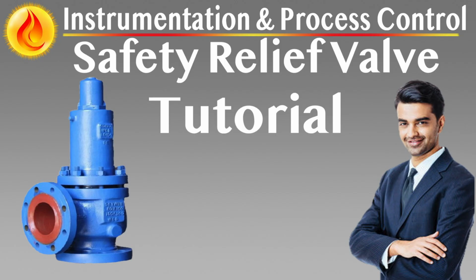Regulatory and code compliance. Air-assisted relief valves are not defined in most pressure vessel codes, e.g. ASME Section 8. Their use may require approval from local authorities or independent inspection bodies, compliance with Instrumented Pressure Protection System (IPPS) methodologies. "Selection and design must be aligned with recognized risk assessment and HAZOP review processes to validate integrity and fault tolerance."